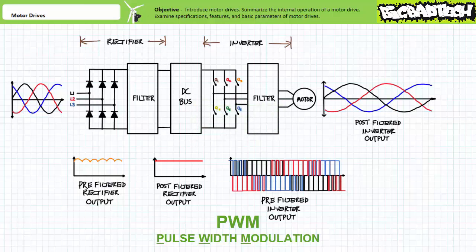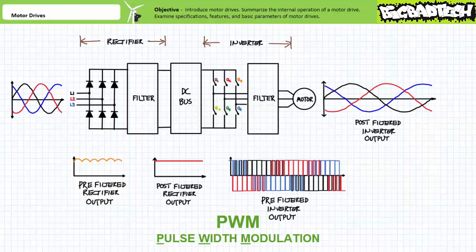For now: a motor drive accepts incoming three-phase AC with a fixed magnitude and frequency, rectifies it all to DC, then outputs three-phase AC with a variable magnitude and frequency. Realize this rectification and subsequent inversion process is not without its limits, because very often the output of a motor drive is electrically noisy, sometimes characterized by high voltage spikes at the output even after filtration.